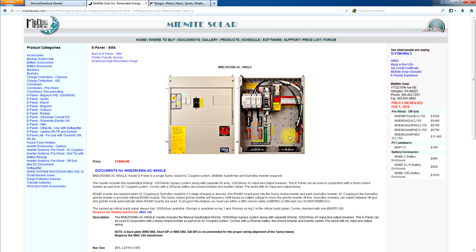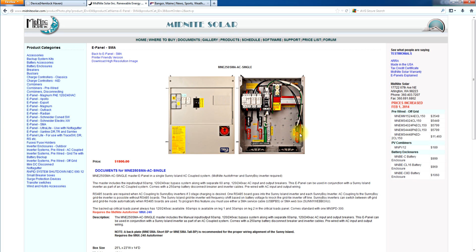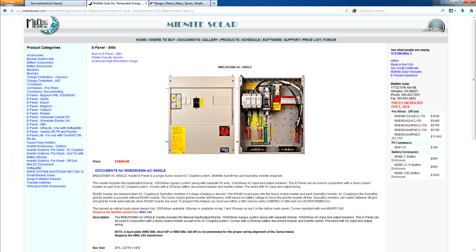Basically what that means is you have the extra bus bars over here and the extra breaker for the Sunny Boy input, or any grid tie inverter for that matter. But the Sunny Boy works particularly well with the Sunny Island. And all ready to go. This is good for 6KW of Sunny Boy into a 6KW Sunny Island. And this is also set up with the special bypass to disconnect the auto former and bypass the inverter if you need it.